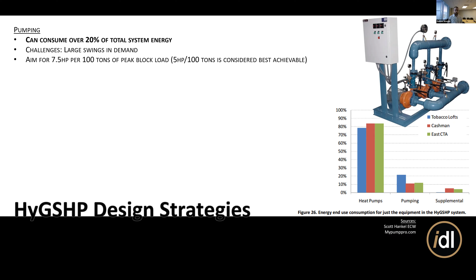Another way to reduce some of the pumping energy is to look at the glycol mixture. It's more viscous, it's more syrupy, it's harder to pump through. Of course, the higher the percentage of, say, brine or antifreeze you have in there, then the colder it can be and the less you have to worry about, especially in a cold environment like, you know, Haley or Ketchum, that it might freeze. But as you increase that, realize that it's going to have an effect on trying to push that more syrupy liquid through all of those coils.